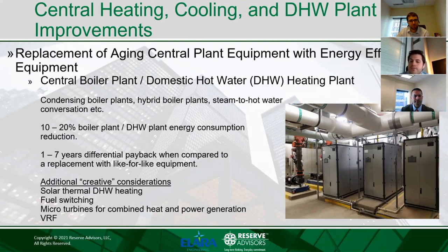I think the term differential payback is important here because as an association, when equipment needs replacement, there's really no do-nothing option here. And as I mentioned earlier, when the equipment is scheduled for replacement, consideration should be given to installation of the higher efficiency equipment because usually the premium is minimal. So for these types of projects, planning and phasing is critical for successful implementation. Please also note that when this type of equipment is replaced, in addition to energy efficiency, we should always think about improving redundancy, comfort, and reducing maintenance expenses as well.